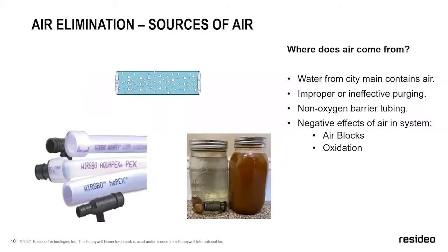When you're looking at air, there's a couple different sources. So when you first fill a system, you're filling it with an air and water mixture. So if you tie it up to the city main, or even if you're filling it from a bucket, you're actually pumping in an air and water mixture. So over time, as the system sits stagnant, what'll happen is all those little air bubbles will start to kind of clump together as the system sits stagnant, which will create much larger bubbles.